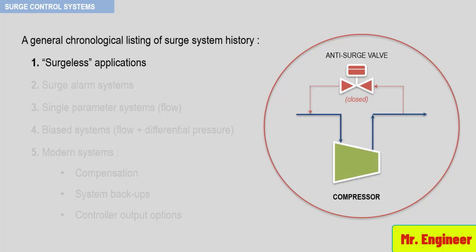If the molecular weight and gas inlet temperature are constant, and the compressor will not be subjected to mechanical damage or fouling, then this assessment is totally true. However, if any of these facts can occur, the compressor in question can be forced into surge, as a result of the inability of the compressor to produce the energy required for the throughput flow. Recall that the operating point of any compressor is the equilibrium between required process system energy and the compressor produced energy. Keep in mind that both of them can change and will certainly do.